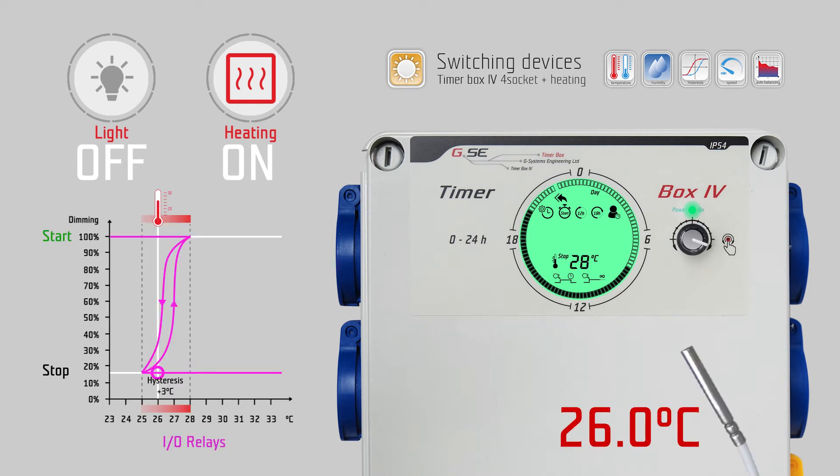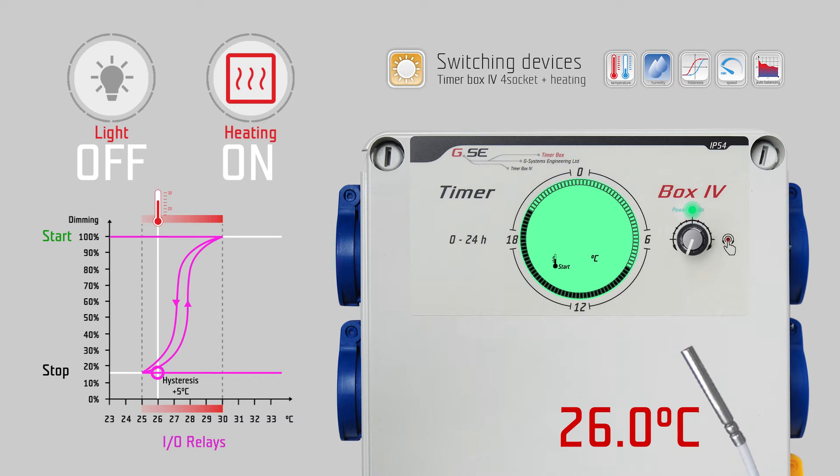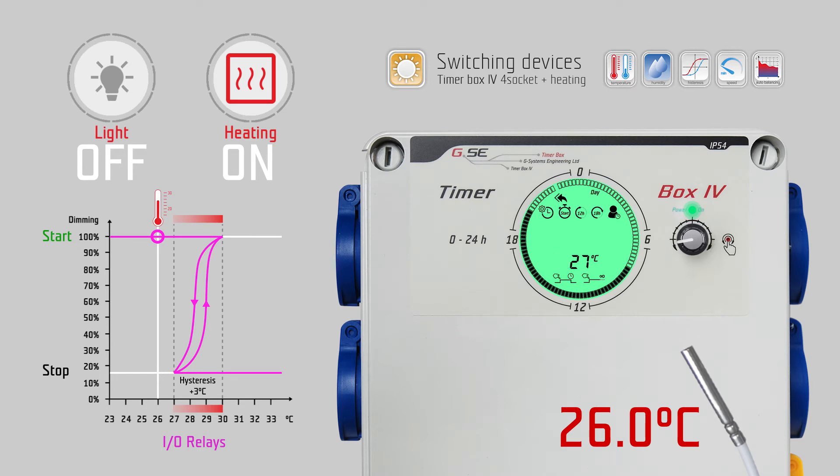Turn right to go to the stop temperature and push the encoder to select. The temperature digits start flashing and the STOP text is shining, indicating stop by temperature. We set this to 28 degrees Celsius and push the encoder to save. The next temperature digits start flashing and the START text is shining, indicating start by temperature. We set this to 27 degrees Celsius and push the encoder to save. Note: the start temperature cannot be greater than minus 1 degree of the stop temperature.